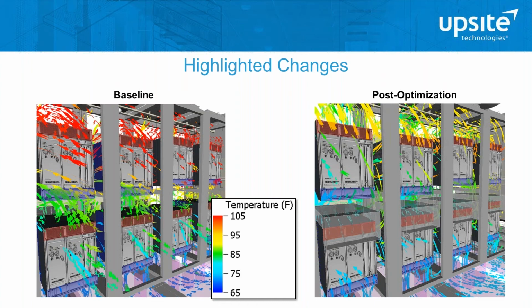Oh yeah, absolutely, just a very clear point. For those who are Fahrenheit focused, 11 degrees C is just like 52 degrees Fahrenheit. It's still not uncommon for me to find supply temperatures in data centers in the high 50s, low 60s, which is extraordinarily cold - well below what ASHRAE suggests as a minimum intake temperature of 64 degrees.